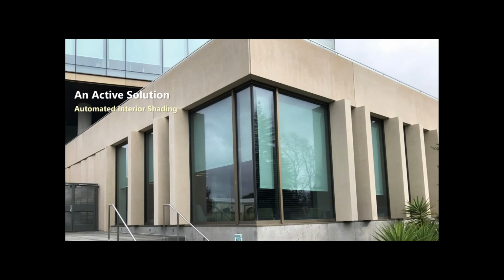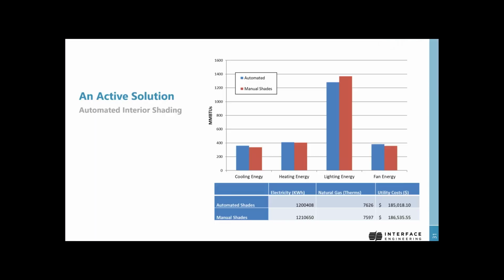And so what this did for Intuit is, first off, it does realize an energy savings. If you compare automated shades versus manual shades, the idea being with manual shades, most likely, and what the research shows, is that occupants will come lower their shades to alleviate the glare condition or that direct solar gain, and they will leave them down longer than they should be. And so what that typically does is negatively impact lighting energy, so you don't have as much daylighting to harvest, and your annual lighting consumption will go up.